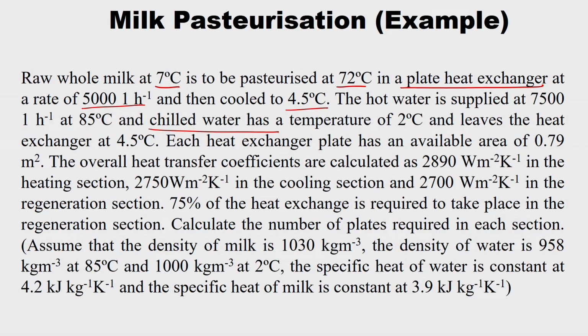Each heat exchanger plate has an available area of 0.79 meter square. The overall heat transfer coefficients are calculated as 2890 watt per meter squared Kelvin in the heating section. The same overall heat transfer coefficient is given for cooling section as well, which is 2750 watt per meter squared Kelvin, and 2700 watt per meter squared Kelvin in the regeneration section.